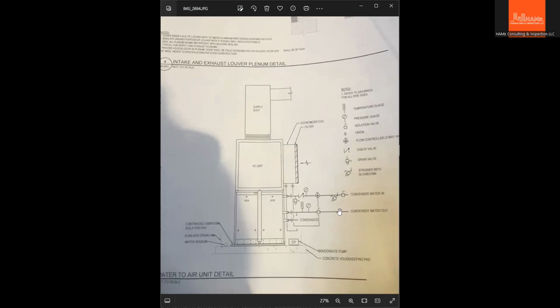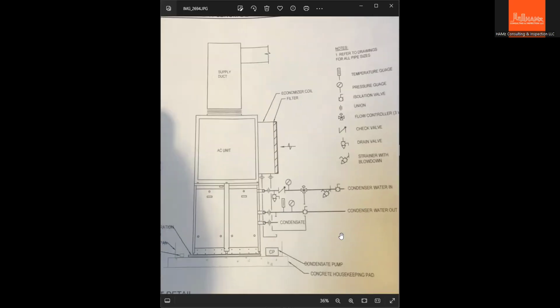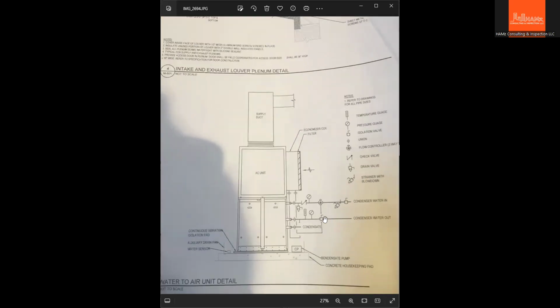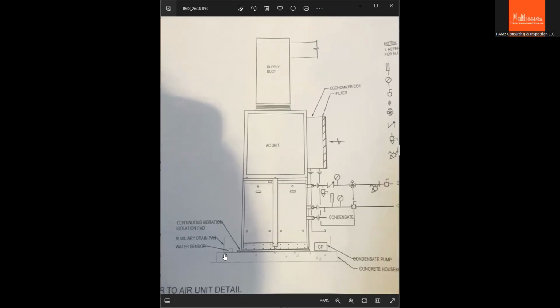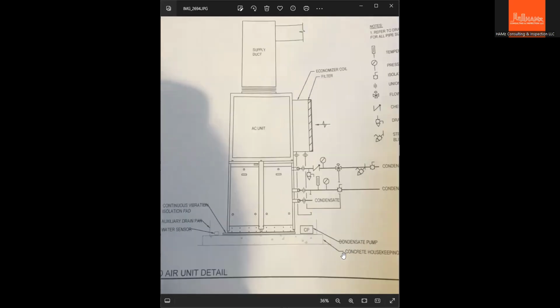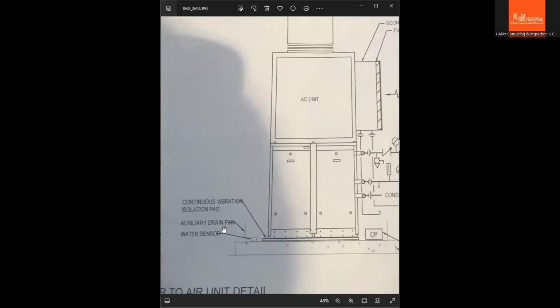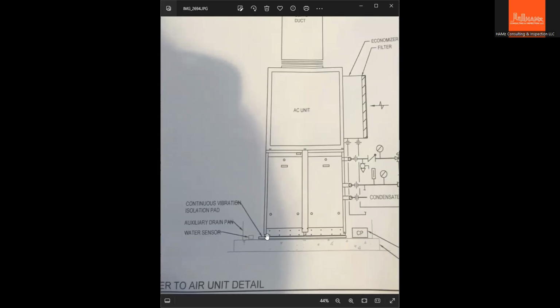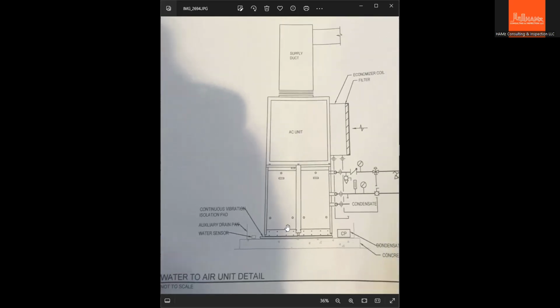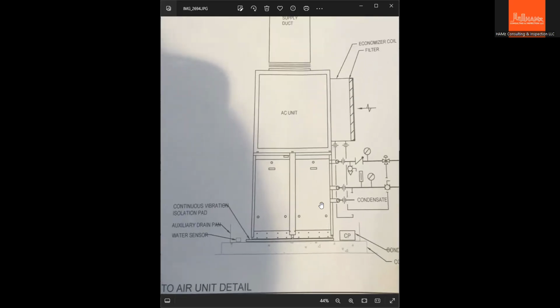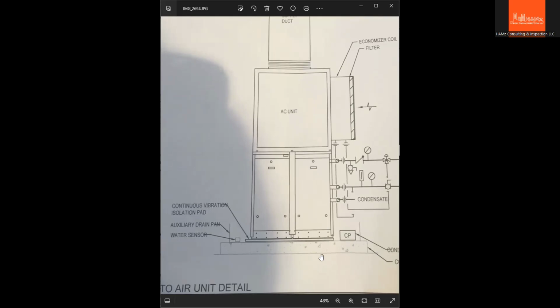And then, okay, so this is the drawing details for the equipment installation. So that's the condensed water, the chill water, in and out. And verify the equipment that is required for the installation. We have the condensate pump, the concrete housekeeping pad, auxiliary drain pan, water sensor, and a vibration isolator. It's a neoprene pad only, a rubber that will absorb in case this equipment vibrates. It's not going to make any noise, and it's not going to break your concrete pad. So that is for the absorption of the vibration.